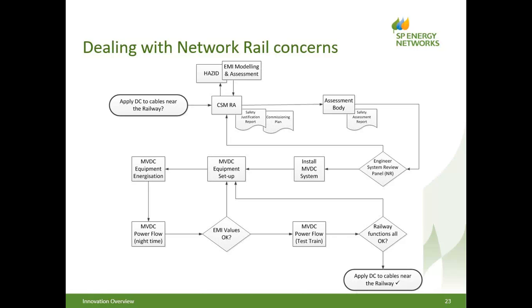If not, there is an opportunity to tweak some of the software firing angles on the thyristor and shift the firing frequencies, which might give us an area of frequency which is less prone to interference than the ones that we would normally run with. So that's one cheaper option to hopefully not give any problems of interference.